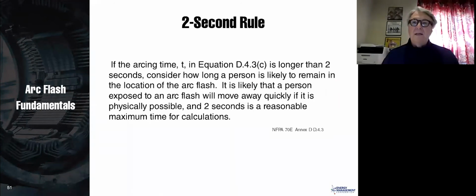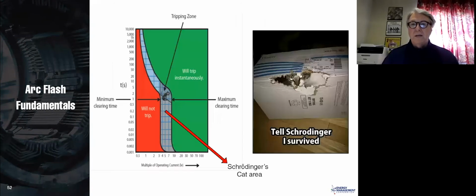It is likely that a person exposed to an arc flash will move away quickly if it is physically possible, and 2 seconds is a reasonable maximum time for calculations. So when you're using Easy Power or SKM or any of those, this 2-second rule tends to be the default. If you think there's no way a person could get out of the area in 2 seconds, you can change that, but that tends to be typical for people doing arc flash studies.